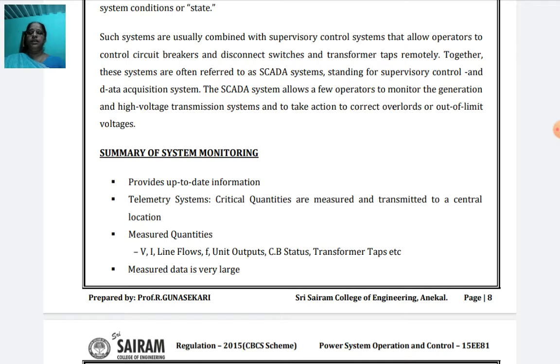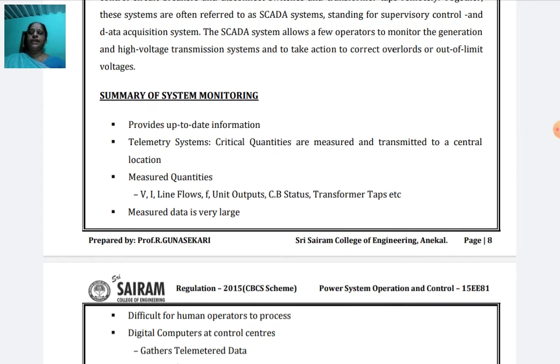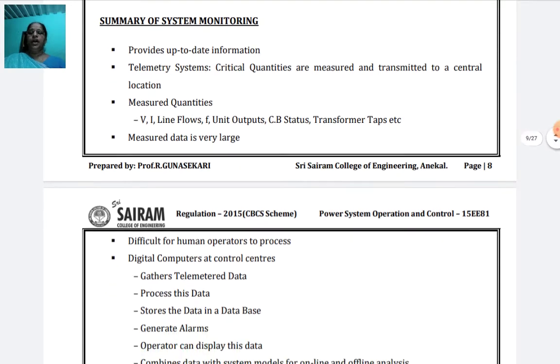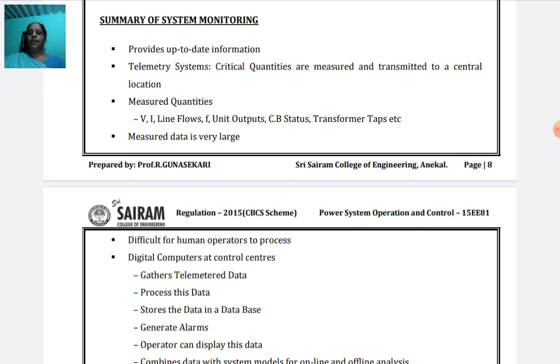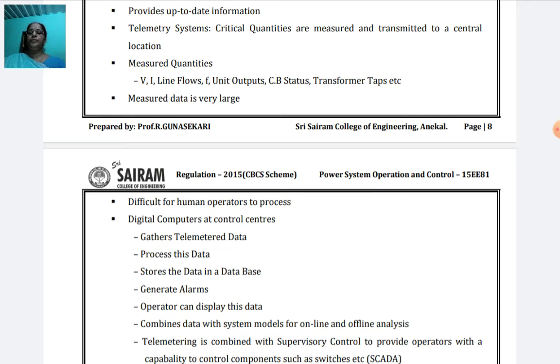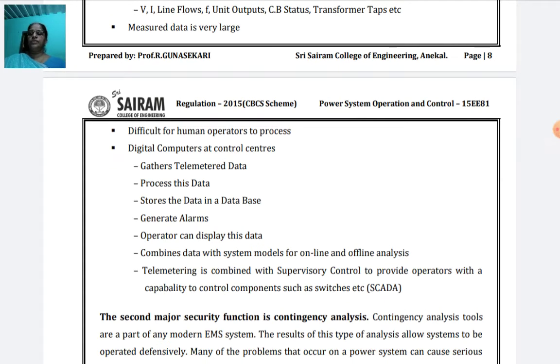Second one is telemetry systems. Third one is measured quantity. Measured quantity means voltage, current, line flows, frequency, unit outputs, that is generator output, circuit breaker status, transformer tap change positions, everything. The measured data is very large and difficult for a human operator to process, so digital computers are used at control centers. For what purpose do we use digital computers at the control center in the power system? First, to gather telemetered data, process this data, store the data in the database, and generate alarms. Then the operator can display this data and combine it with system models for online and offline analysis. Telemetry is combined with SCADA to control components such as switches. This is the system monitoring function of power system security.